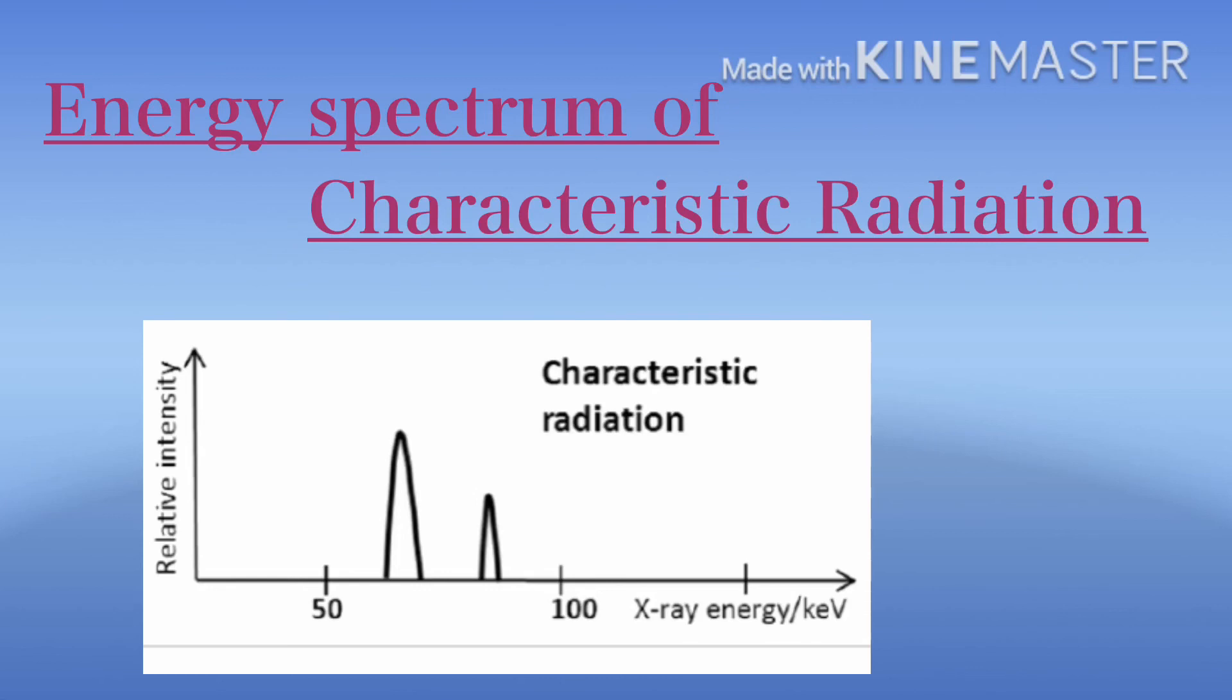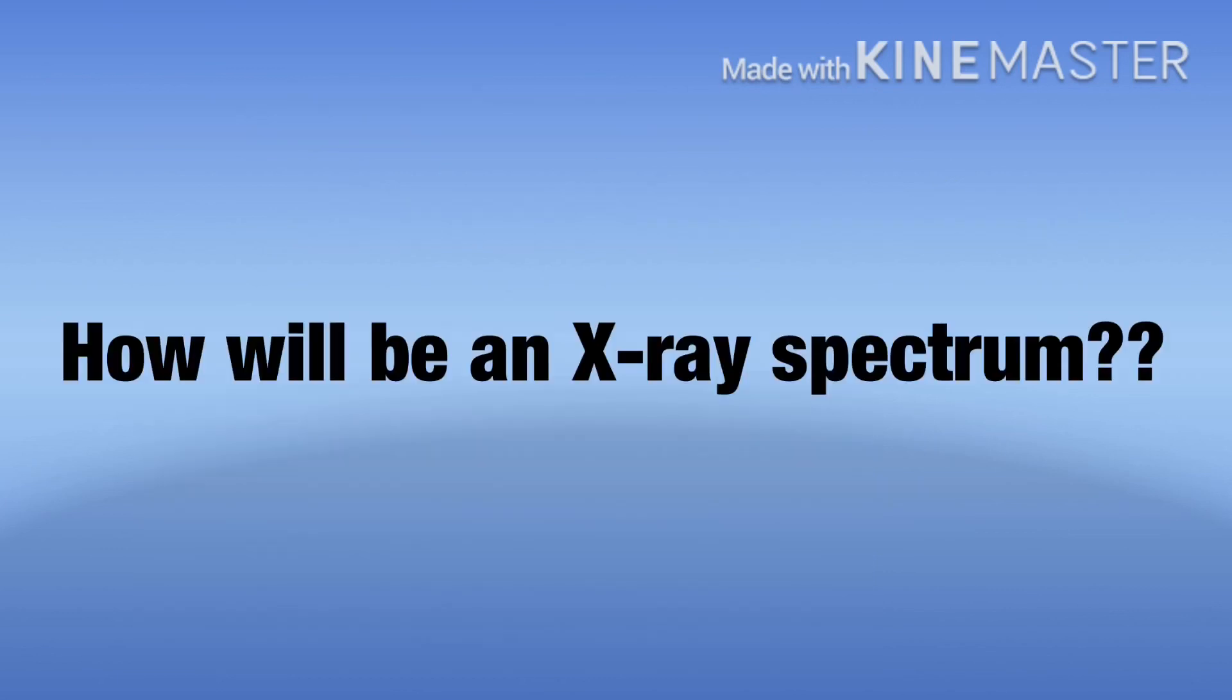For example, electron transition in the case of tungsten anode: electron transition from the L shell to K shell produces X-ray photons of 57.98 and 59.32 keV.